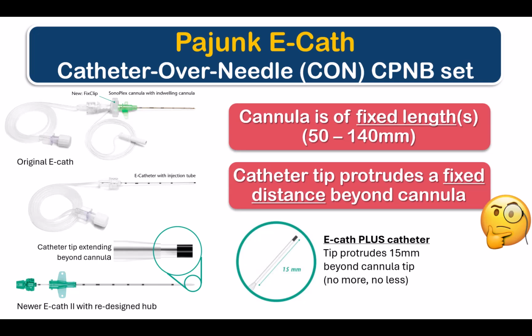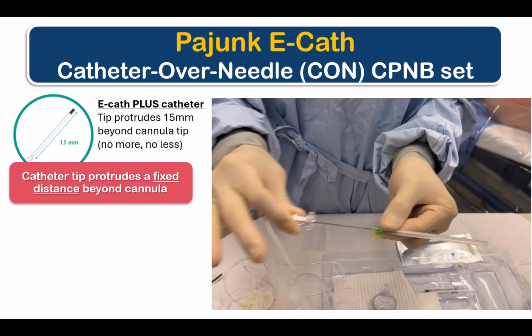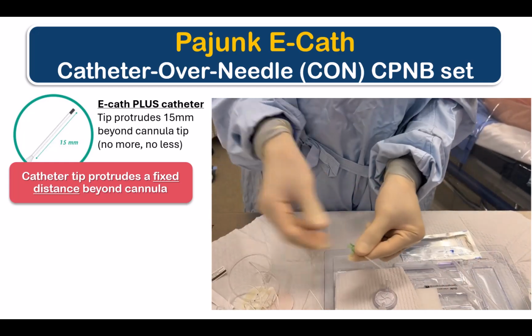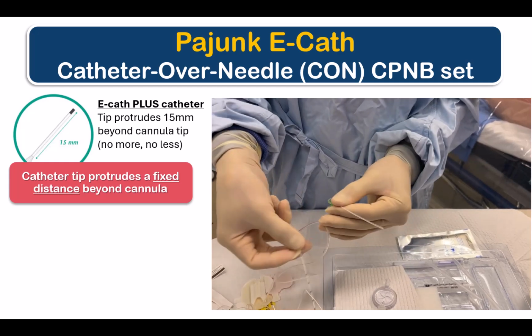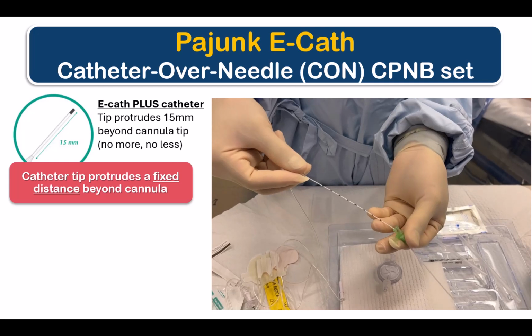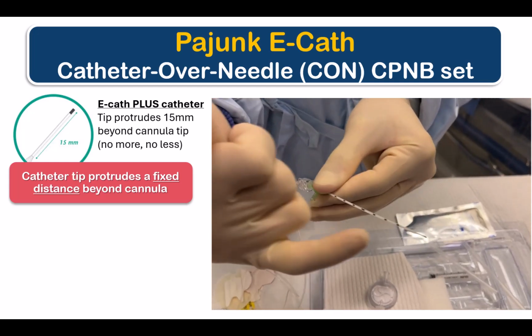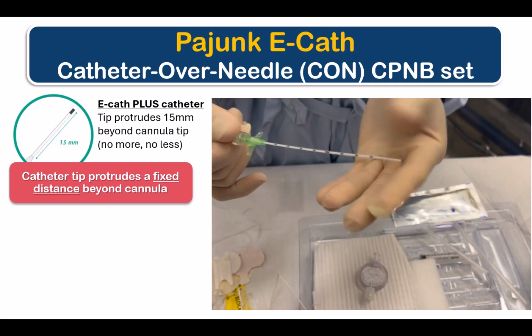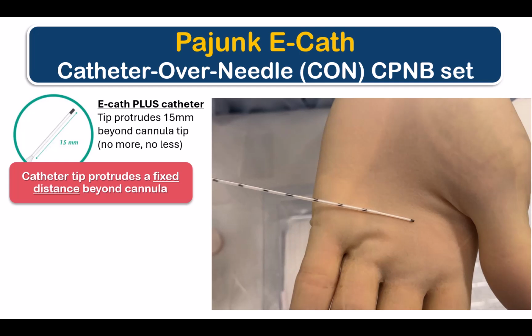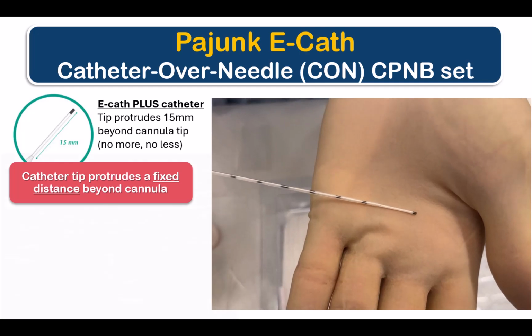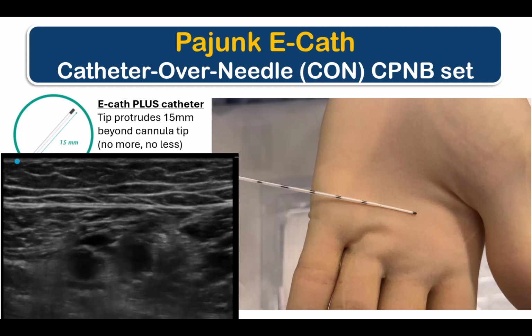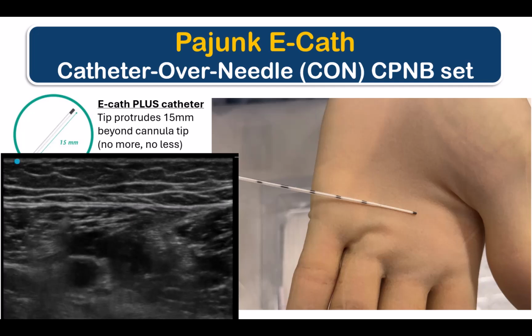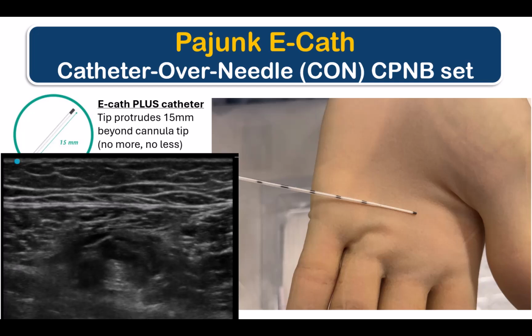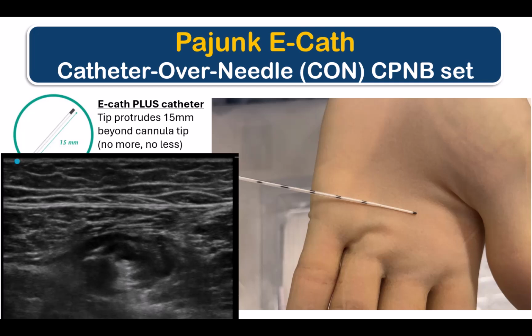More recently, a version called the E-Cath Plus catheter was introduced to help address the risk of dislodgement. The inner cannula of the Plus version extends 15 millimeters beyond the tip of the introducer cannula. This is shown here. Note, however, that this is again a fixed distance. If there's any obstruction preventing the catheter from extending this distance, you will not be able to lock the catheter and introducer hubs together. So it's critical that there is sufficient space beyond the stylet needle tip for the catheter to advance into. And generally, we create this by hydrodissection with a loading bolus of local anesthetic.